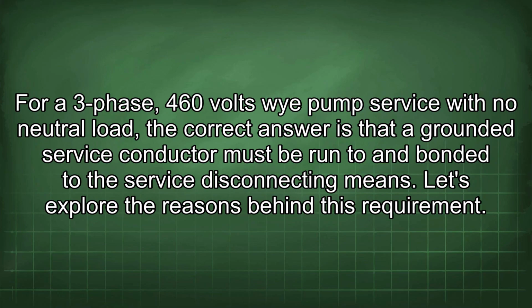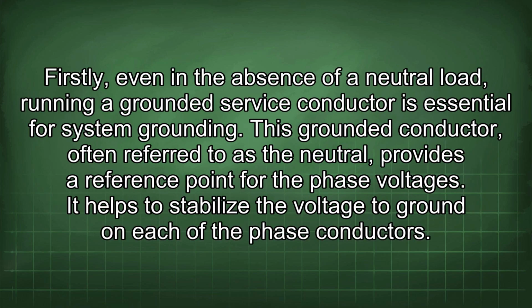For a three-phase 460 volts Y pump service with no neutral load, the correct answer is that a grounded service conductor must be run to and bonded to the service disconnecting means. Let's explore the reasons behind this requirement. Firstly, even in the absence of a neutral load, running a grounded service conductor is essential for system grounding.